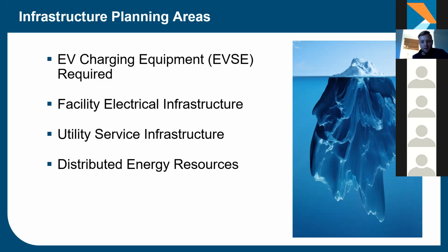One more thing on the utility service infrastructure. Sometimes when you get going with your utility, there might be a cost. Say you're going to install a fast charger, and there's no three-phase facility nearby. So there may be what we call a cost in aid of construction. CIAC is what people will call that. You may have an upfront service cost to get that facility installed. So just be aware of that. That's the point of working with your utility early on, so you really understand what costs you're looking at. Let's go to the next slide, please.